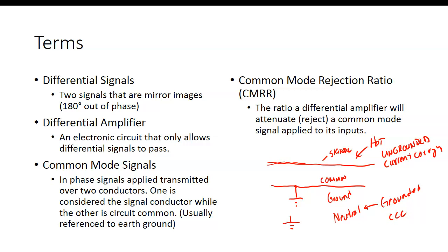And then we have a ground. So this guy is not supposed to carry current. Your ground lead is not supposed to carry current. Your neutral is a current carrying conductor that's referenced to ground. So the difference between the ground and the neutral is the neutral carries current, and this guy's not supposed to, unless something's wrong. So if your true ground carries current, something's wrong.